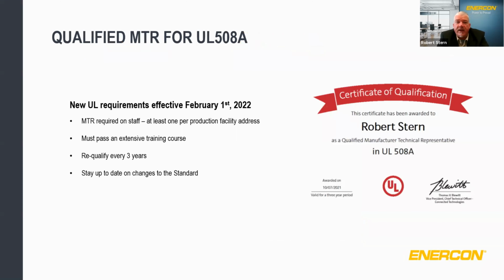So something that's brand new for the UL508A standard is that, effective February 1st, every production location you have has to have a qualified MTR on staff. And that's by address. So if you have multiple production addresses, you need to have an MTR at each address. To become a qualified MTR, you have to pass an extensive training course, and you have to requalify every 3 years. And you have to stay up to date on changes to the standard so that you can make sure all the product coming out of that facility is going to be in compliance. And next page.